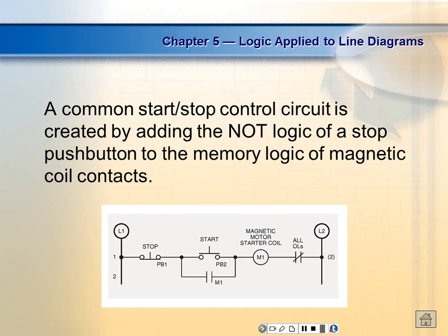So how does this work? Hit the start button, or the seal-in contact. Yeah, that's an OR, right? So if M1 is closed, the load will be energized. If the start button is closed, the load will be energized. By the way, this is a start button, and you have to be careful about your book. It looks pretty close to a normally closed, but remember, normally closed, the lines are drawn under the dots. Normally open, it's just that they draw them real close.